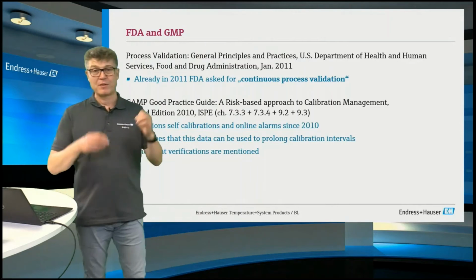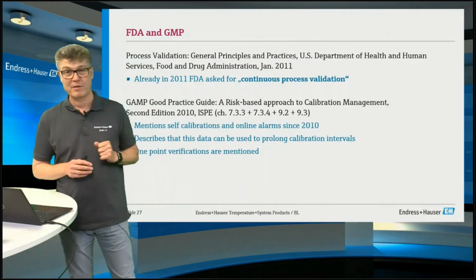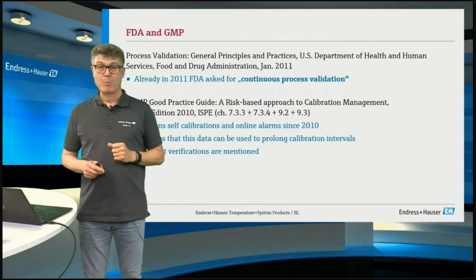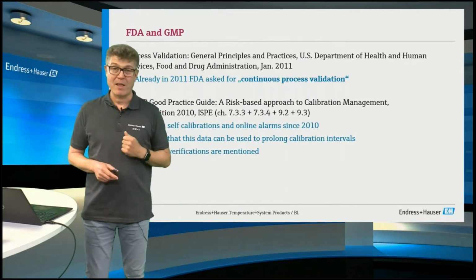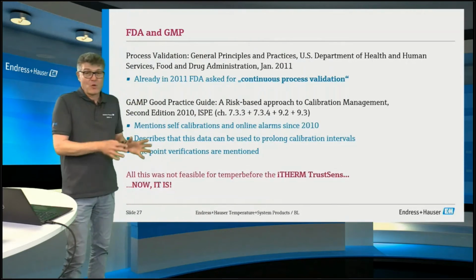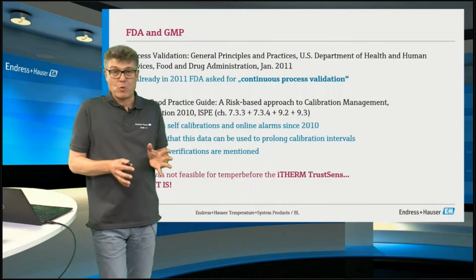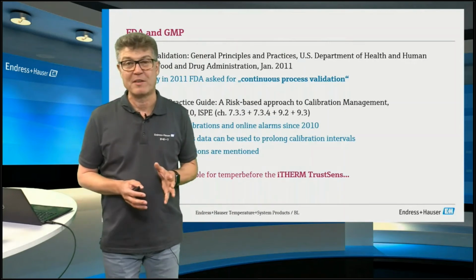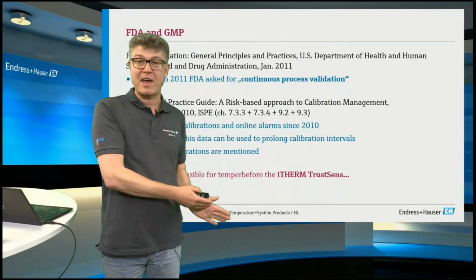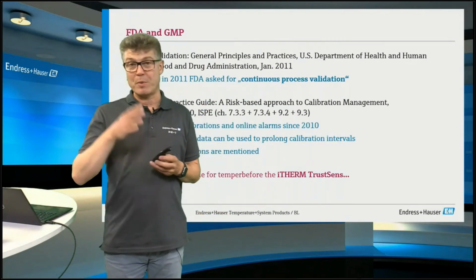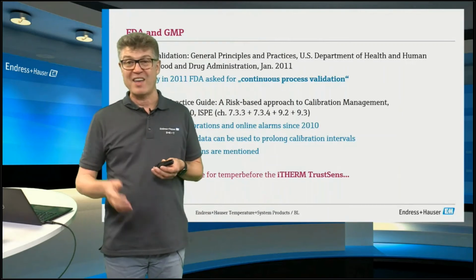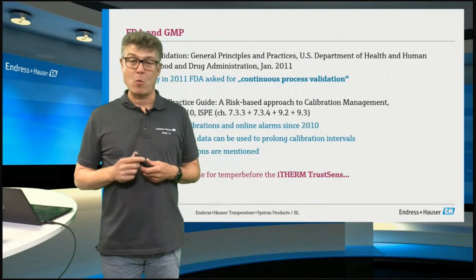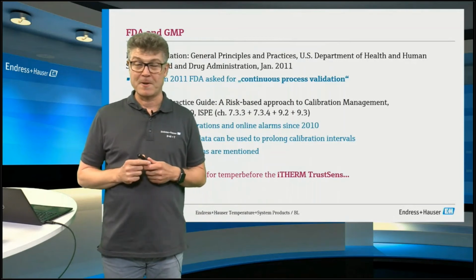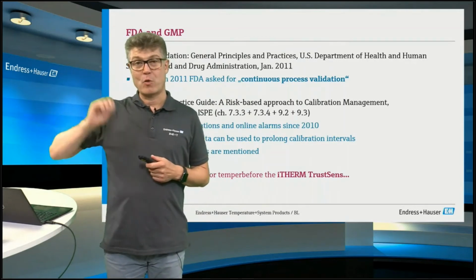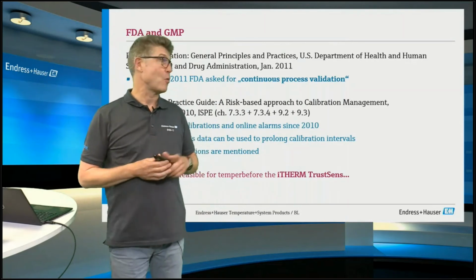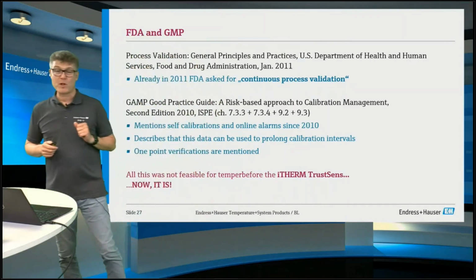1-point verifications have been mentioned in this document 11 years ago. What we have is 1-point calibrations, better than asked. So it's not that the FDA or the GMP rules say you cannot use it. It's the opposite. They have been asking for it for a decade, and now it is there. So the question of the auditor will be someday, there is a better technology, why don't you use it to reduce the risk? Because every time a cooling means a calibration. So it's the opposite. The GMP would love it.